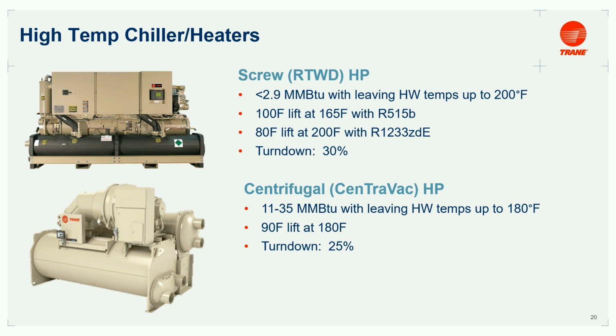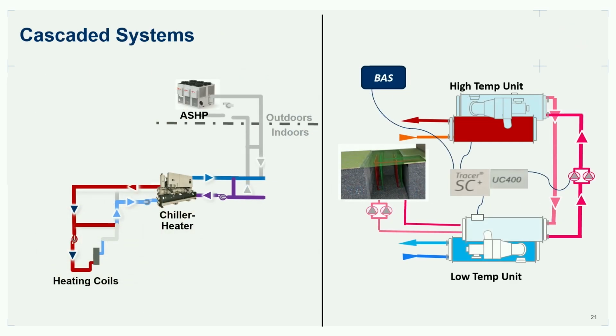When I talk about the system side, we're trying to innovate a little bit, and some of this is based on the challenges with lift. Compressors often don't really care about the temperature as much as that lift. Centrifugal compressors typically max out around 75 degrees of lift, screws you can get 110, recips we just saw you can get 180. That's pretty impressive. But how can we use standard equipment available today to achieve that?